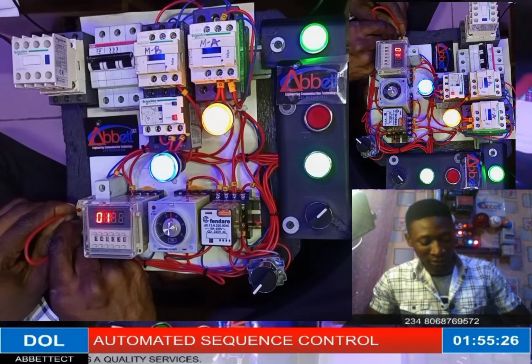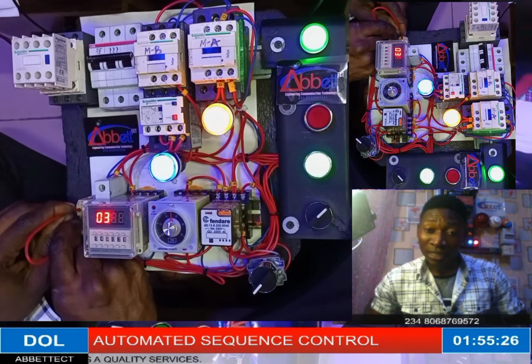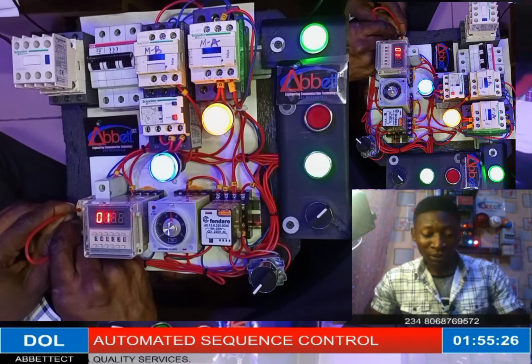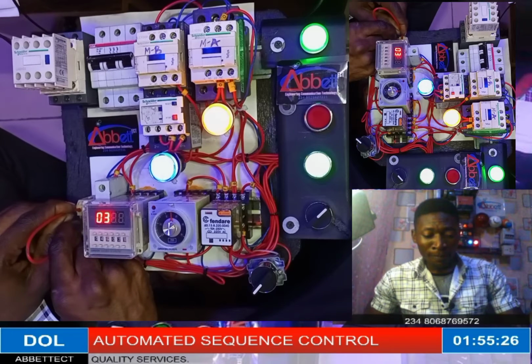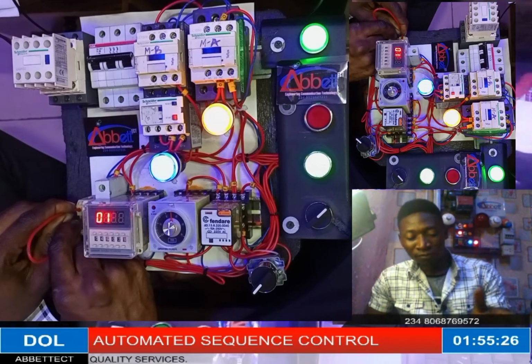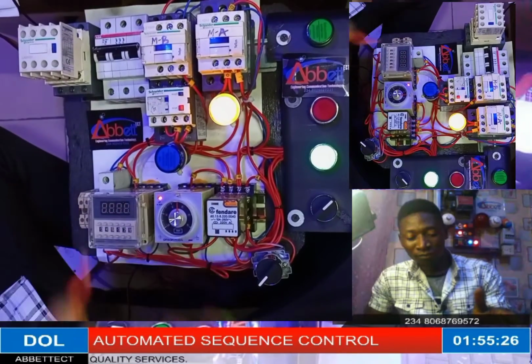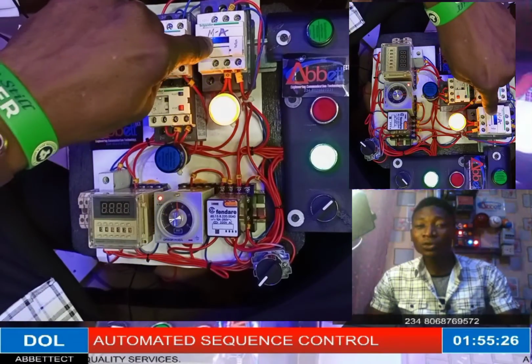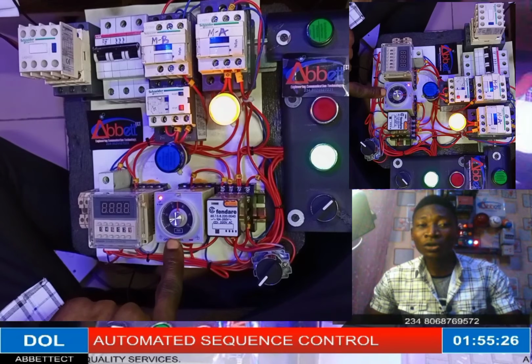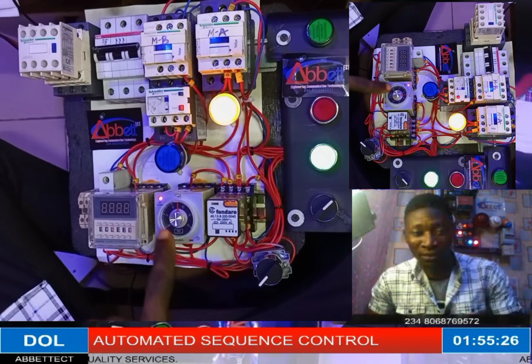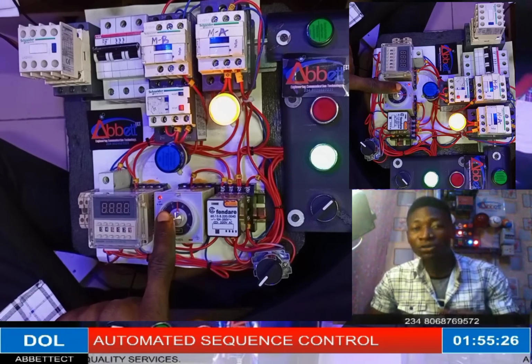This is auto. So it is the sensor in the fridge that will be doing this closing and opening here. When the sensor closes, it will make the system run, and when the sensor opens, it will make the system stop. But this delay time will still function as it used to, depending on the timing here.